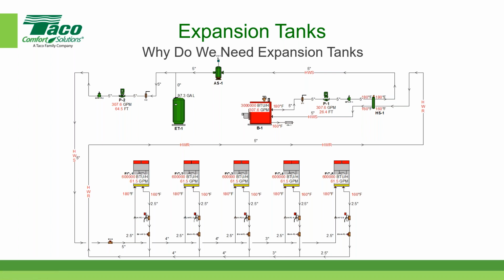So if a tank is missized and they need to add a second tank but are short on space, can they have two different size tanks? Add a smaller one? You can, yes. Although I generally would prefer to have the tanks the same size. The reasoning behind that is that if one of the tanks should fail, if the large tank should fail, now you're left with the small tank, and the small tank won't have enough acceptance volume to keep the system within the proper operating pressure parameters.